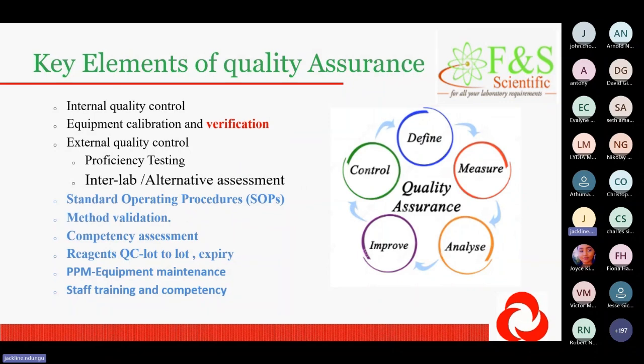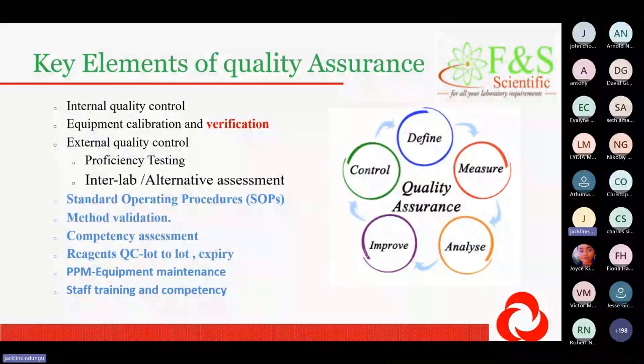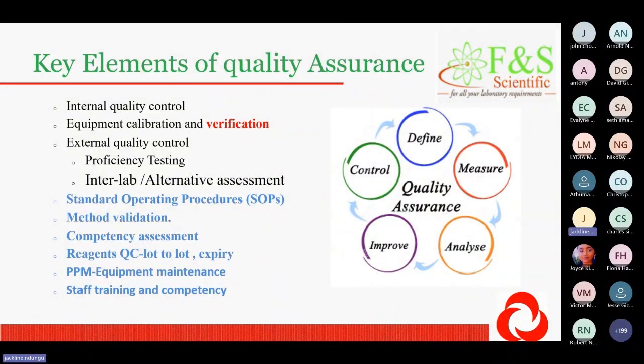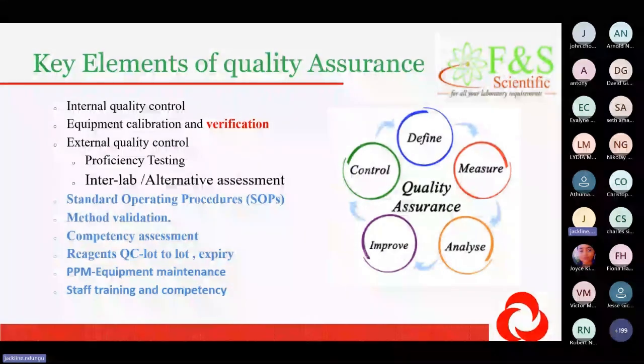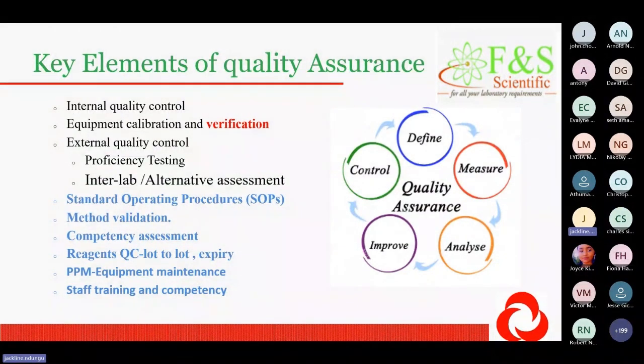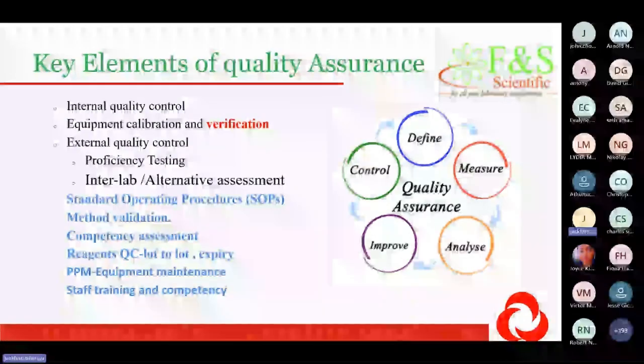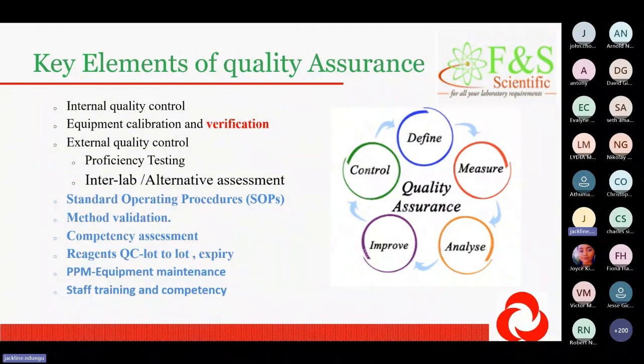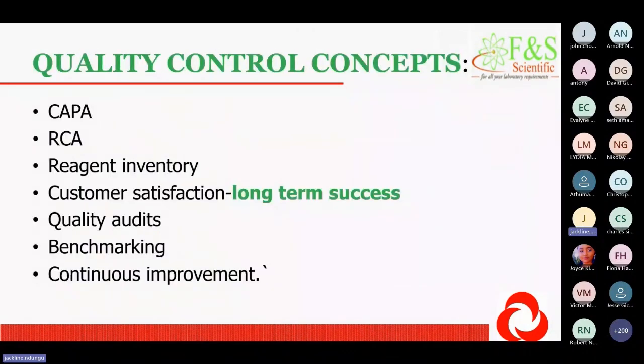So PPM is planned preventive maintenance of the equipment. You make sure that your equipment is maintained well. We are lucky, we have a department that does PPM for us. And apart from that, even if it's a main piece of equipment, let's say from F&S, let's say Bio-Rad, Bio-Rad will maintain the equipment for you. You have a contract on the same, so that they can be coming in. They have to put that as a schedule, and they'll know that maybe they are supposed to maintain this equipment once a year or 2 times a year as per the manufacturer. And again, if the work is too much, then you even increase the maintenance so that your equipment can be efficient. I have mentioned staff training and competency.